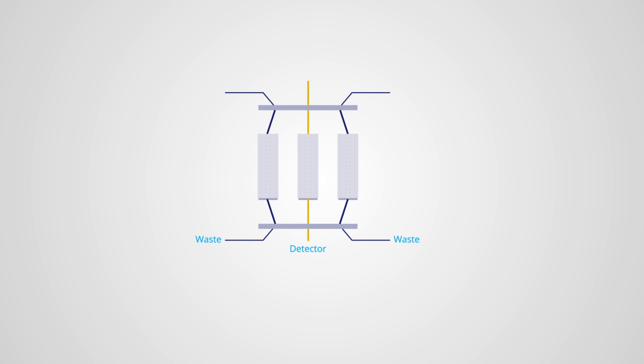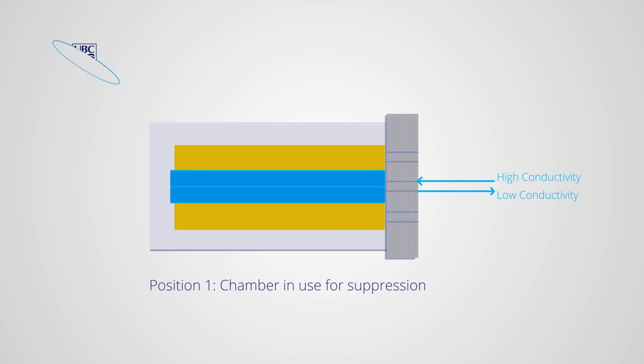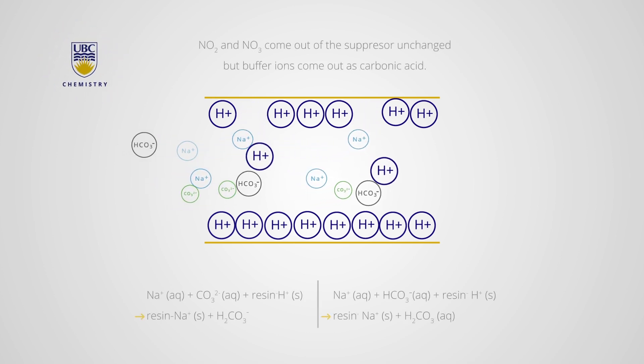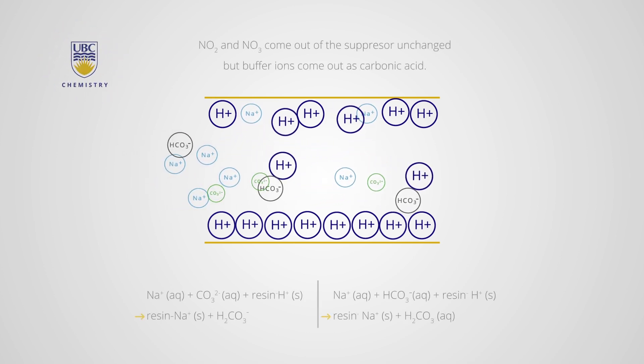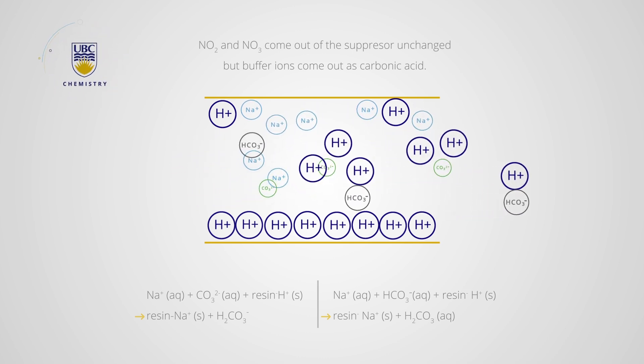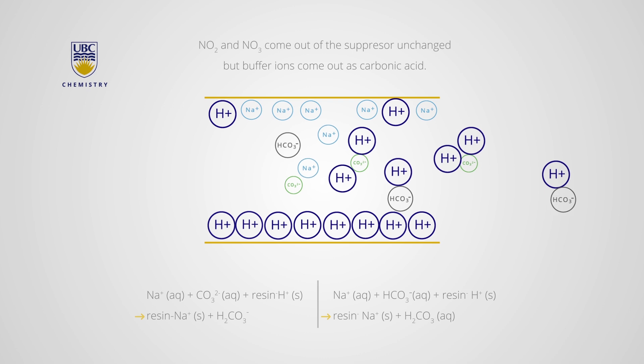The suppressor uses a regeneration process which is carried out in three steps. The first step in the process is where bicarbonate and carbonate anions are converted to carbonic acid. When the analyte comes out of the column, it enters a chamber of the suppressor. Here an ion exchange resin supplies protons which converts the bicarbonate and carbonate anions into carbonic acid.